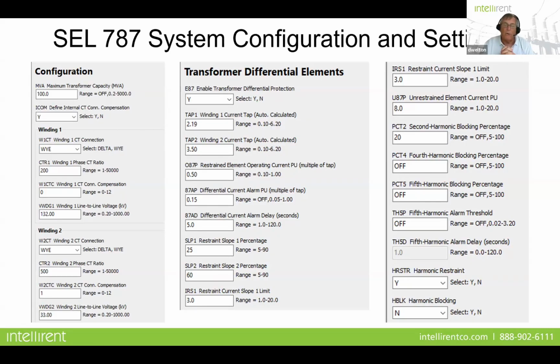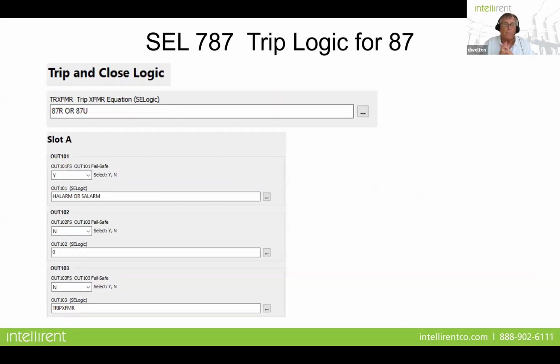The other problem that I run into is you have two groups of people. You have protection engineers that are actually putting the settings into the relay, and you've got a substation crew that's actually going out and testing and validating those settings in the relay. So if you're testing it, you have to rely heavily on the fact that the engineer put those into the relay properly, or properly configured the file that you're going to upload to the relay with these settings in there. So you have to understand that relay testing people, whether you're an engineer or a relay technician, you have to have as much knowledge as you possibly can, because you're the last line of defense to make sure that thing's going to work.